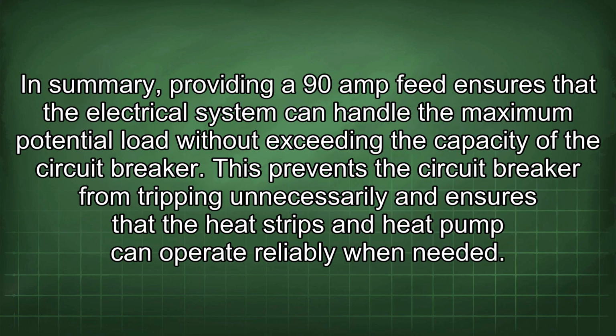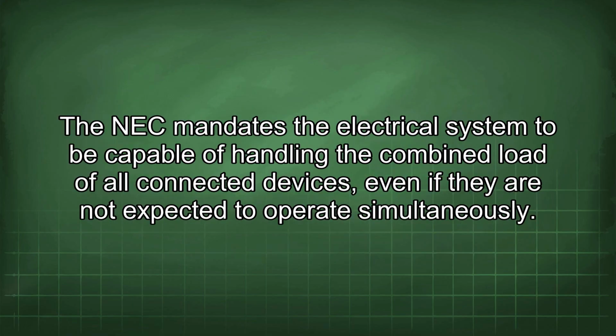In summary, providing a 90 amp feed ensures that the electrical system can handle the maximum potential load without exceeding the capacity of the circuit breaker. This prevents the circuit breaker from tripping unnecessarily and ensures that the heat strips and heat pump can operate reliably when needed. The NEC mandates the electrical system to be capable of handling the combined load of all connected devices, even if they are not expected to operate simultaneously.